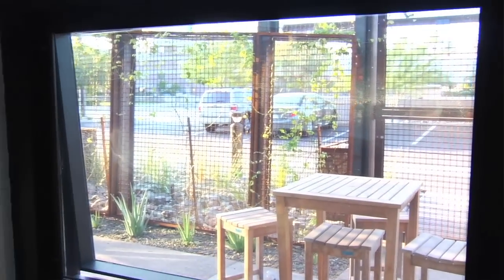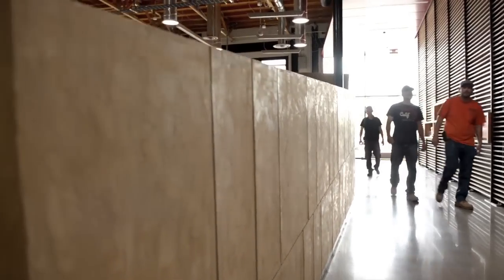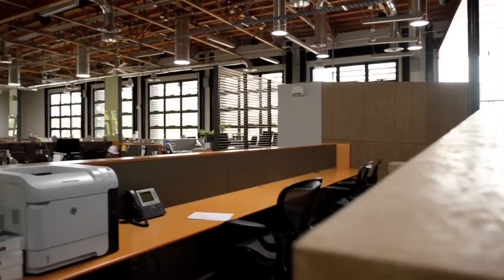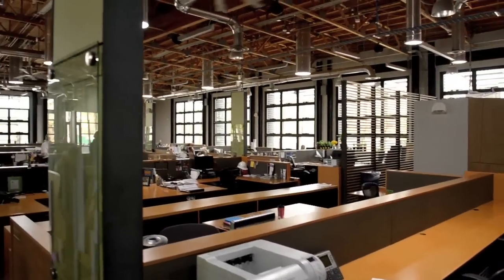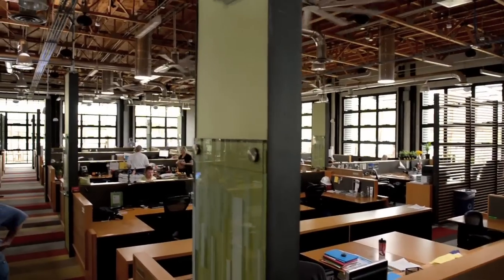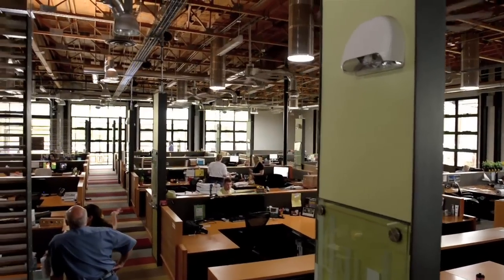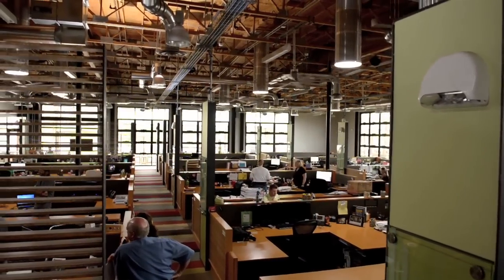All of this information is trend logged into the system front end, and there's a data log of that. By reviewing it with the engineering and commissioning team, we can fine-tune the building. As DPR brings more empirical data forward—how many people were in the building on a given day, were there any issues—certain months of the year we take all that information, analyze it, and adjust the building's parameters through the front-end system.